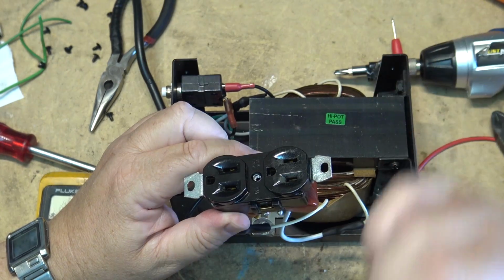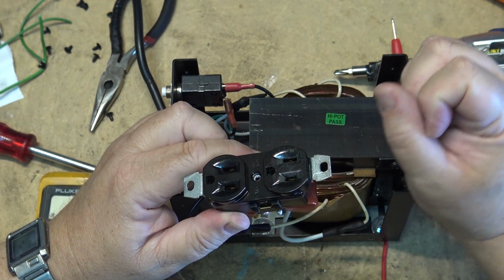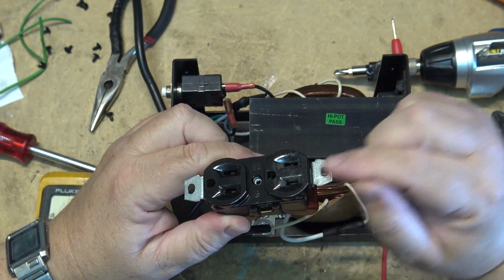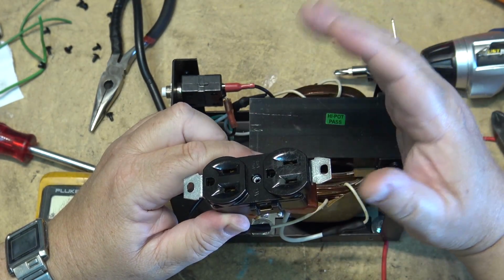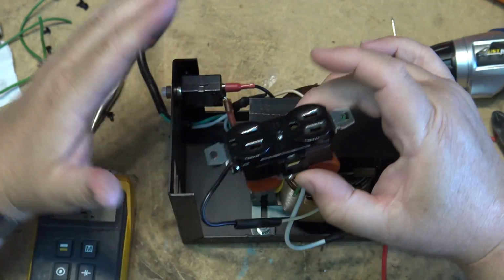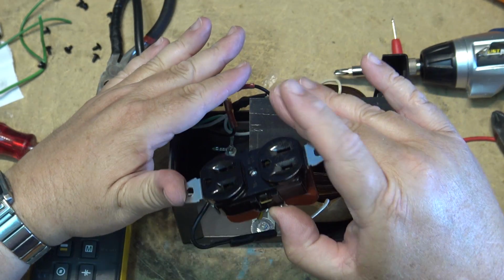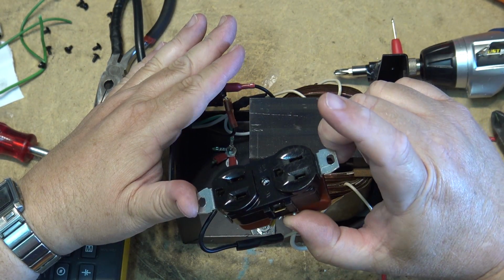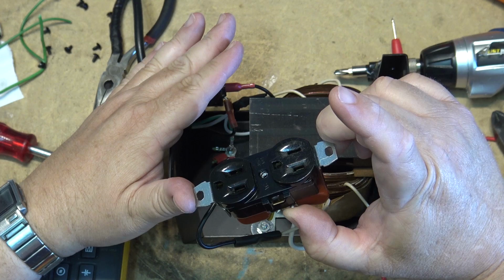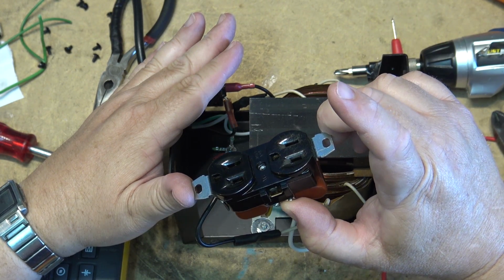If neither one of them is grounded, they will both operate with respect to ground, but isolated at about half the line voltage. But isolated, you can ground either side and you'll have no complete circuit. So I could touch the hot wire and touch ground, and as long as I wasn't touching the return or the neutral at the same time, I'm isolated. That's how an isolation transformer works.